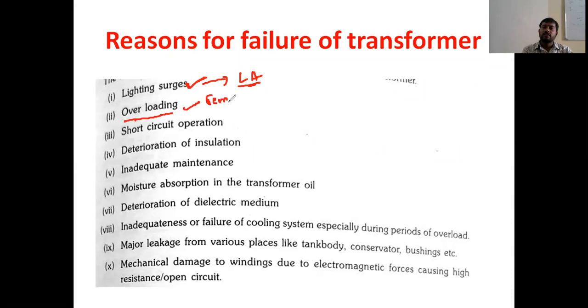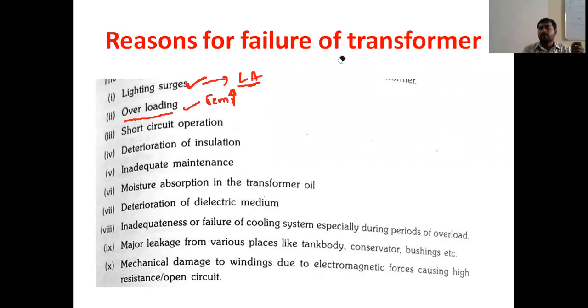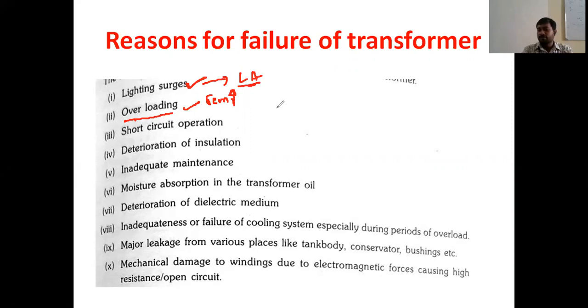Also, overloading. Due to overloading, temperature increases, and the insulation will get burned between the core-to-core laminations and between the winding. That insulation will be damaged, and because of that, the transformer fails.